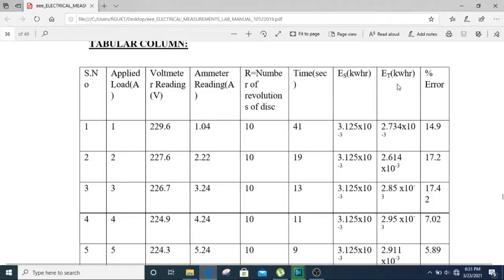Coming to true energy, it is voltmeter reading into ammeter reading into the time taken by the energy meter to complete 10 revolutions. Then you are going to get this much energy, that is the true energy. Voltmeter reading, ammeter reading and time give the true energy. Likewise, you increase the load in steps and note down all the readings.